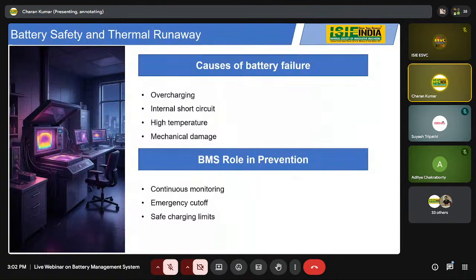Next is internal short circuit. Due to a short circuit, high currents pass through the cell, causing a sudden change in temperature, which again causes thermal runaway. The BMS monitors this as well; if there is any sudden rise in temperature or sudden increase in current in the BMS and battery, it detects this and isolates the system.